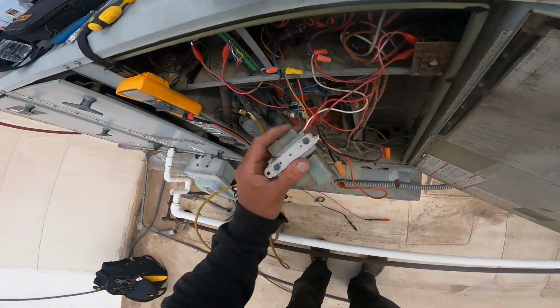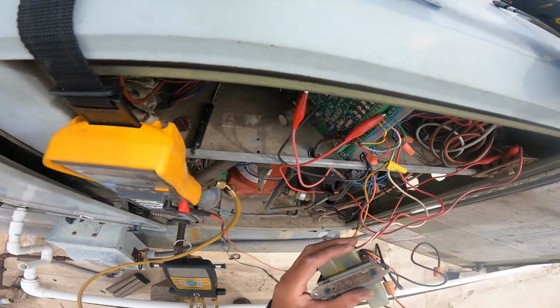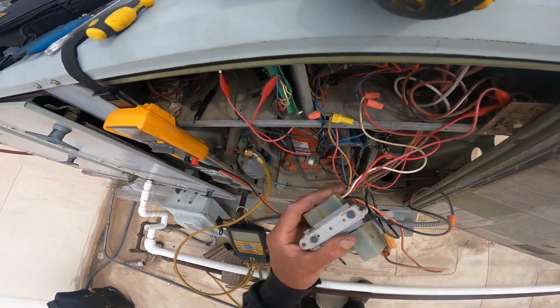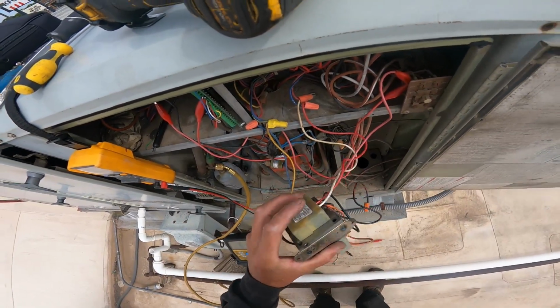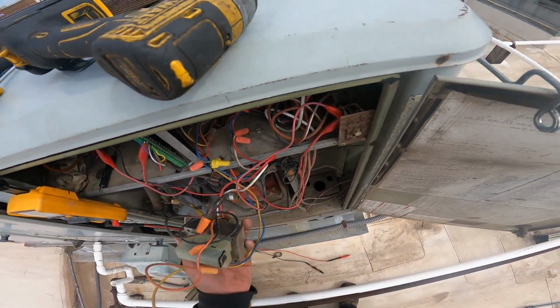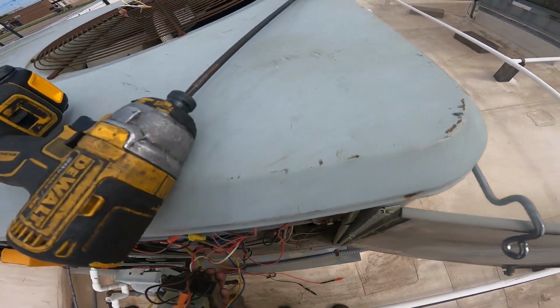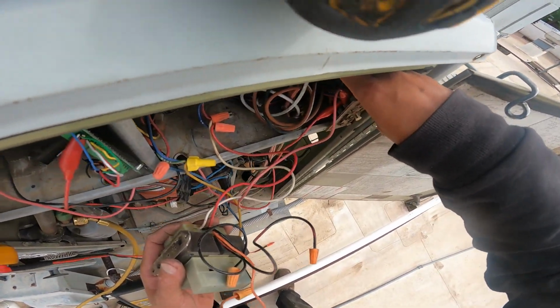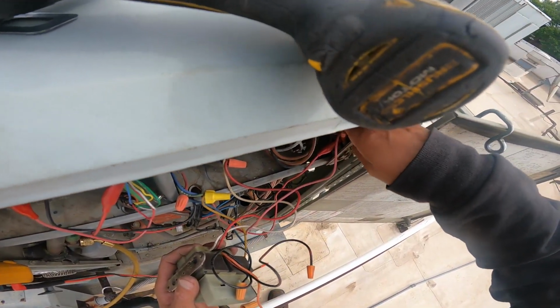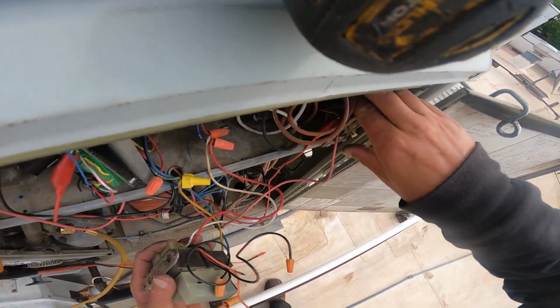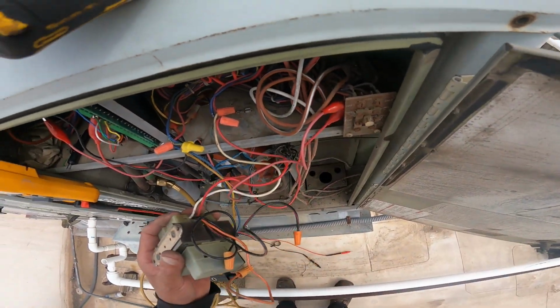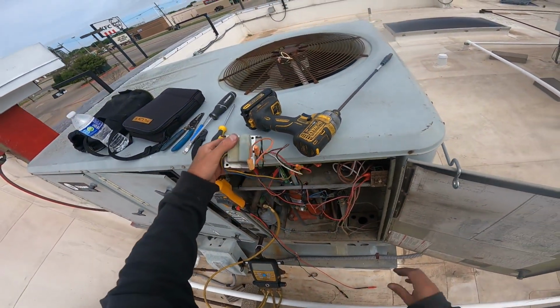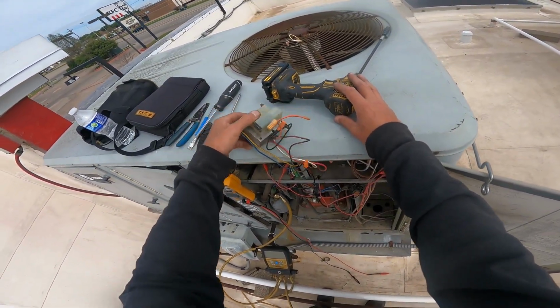It's no wonder that this board ain't working now. You feed 120 volts into a board, you got problems. This transformer was tripped, and somehow I was still getting voltage to the low voltage side, which means there's a chance I have a wire frayed somewhere and it's sitting on a low voltage wire, combining high and low. They taped up that pretty good. Slightly impressive. Somebody put a low voltage wire on a high voltage circuit.